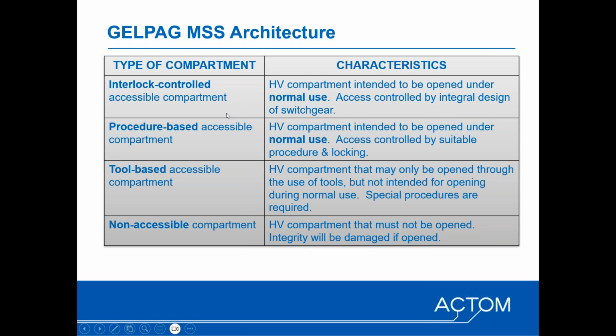So you have interlock-controlled accessible compartments, procedure-based ones, as well as tool-based ones. And I think what's important to note, and it's often missed, is that only interlock-controlled and procedure-based compartments are allowed for normal use. A tool-based accessible compartment can be provided, but should not be. It's not intended to open a tool-based accessible compartment during normal use. Normal use is defined in the IEC as well, and it's also ultimately up to the manufacturer to define what is normal use.